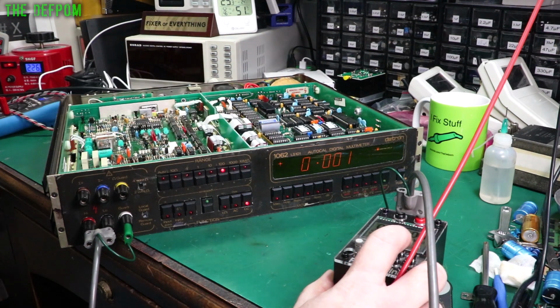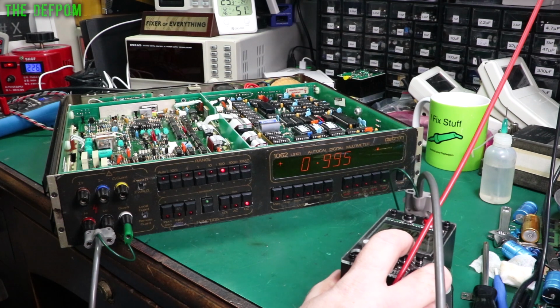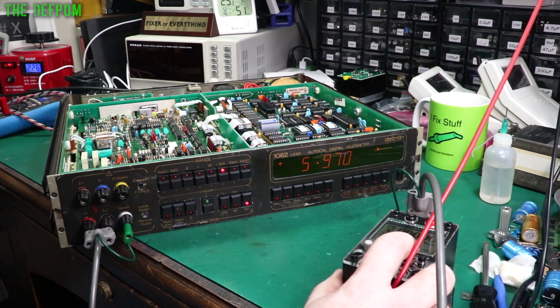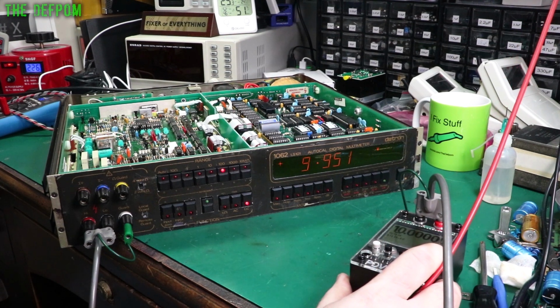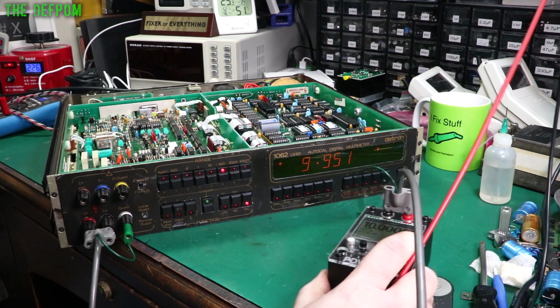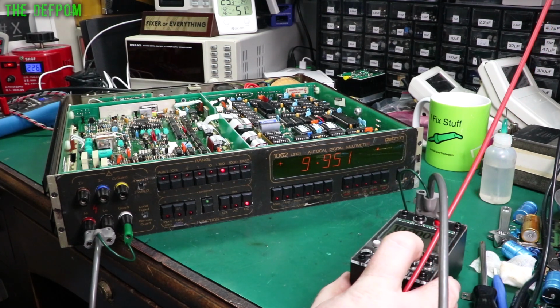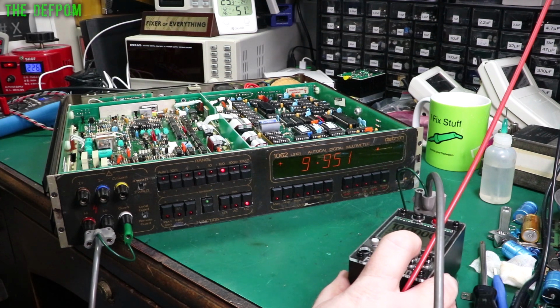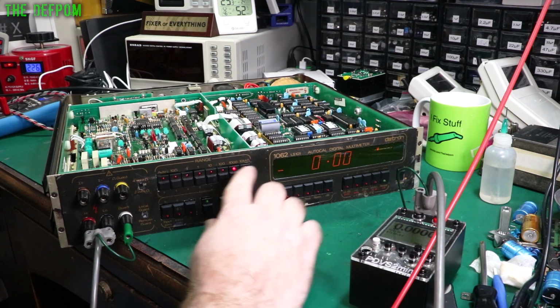The 100 volt range, so that registered, yeah, 995. Do 10 volts on here, and yeah, 9.95. That's out by too much to be a calibration issue. Well, a difference in my calibration data compared to theirs. It's just completely wrong. So anyway, it's working. Let's do 1000 volt range. Is that registering? It is. So yeah, all those ranges are working.